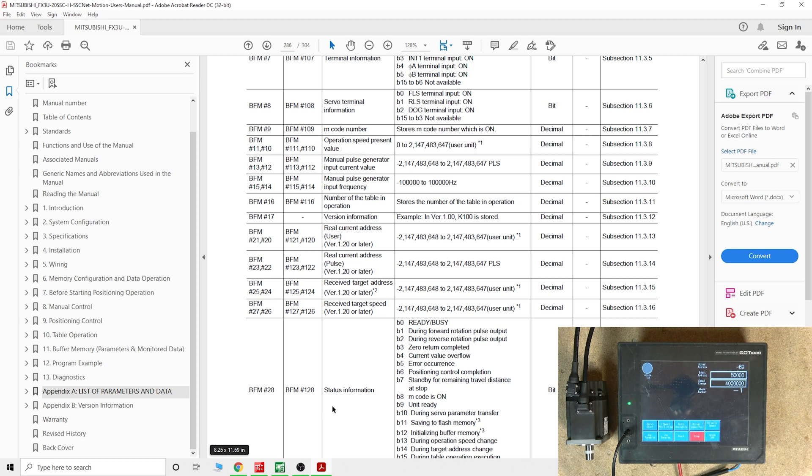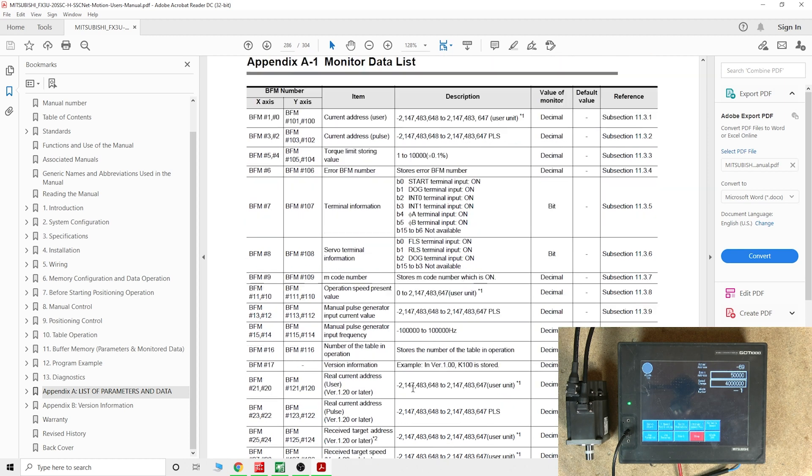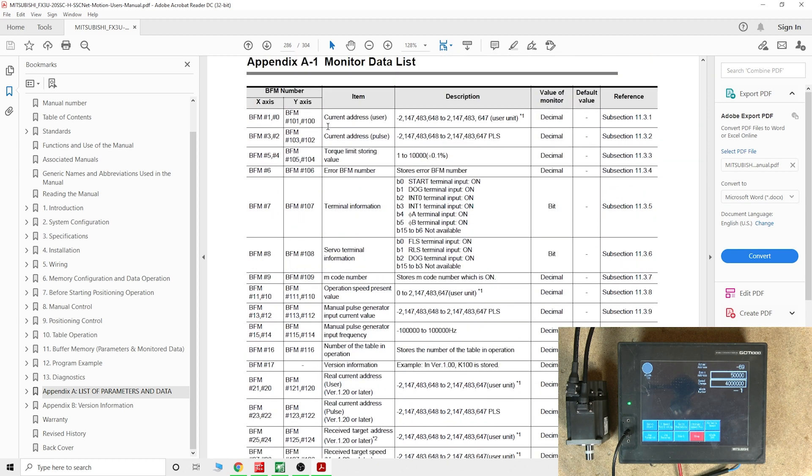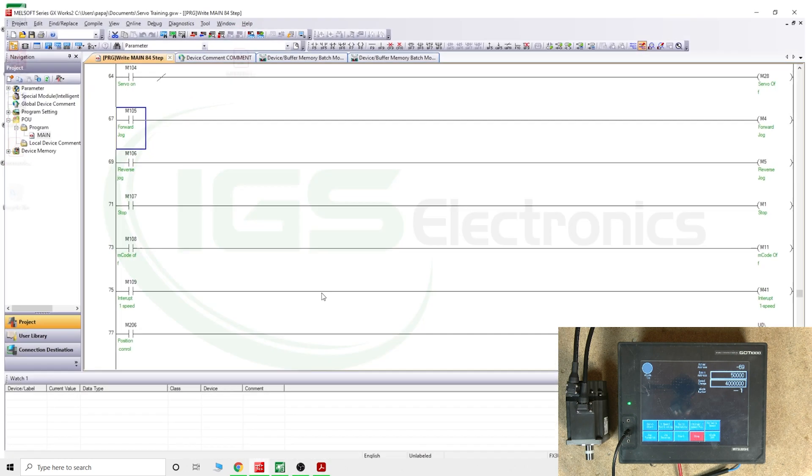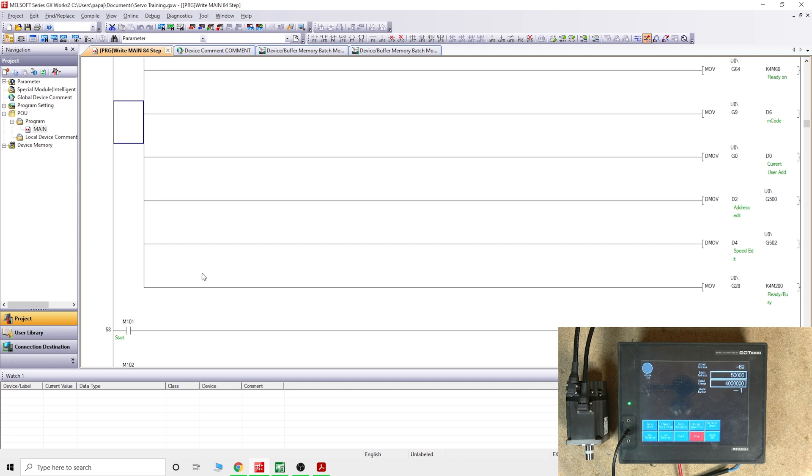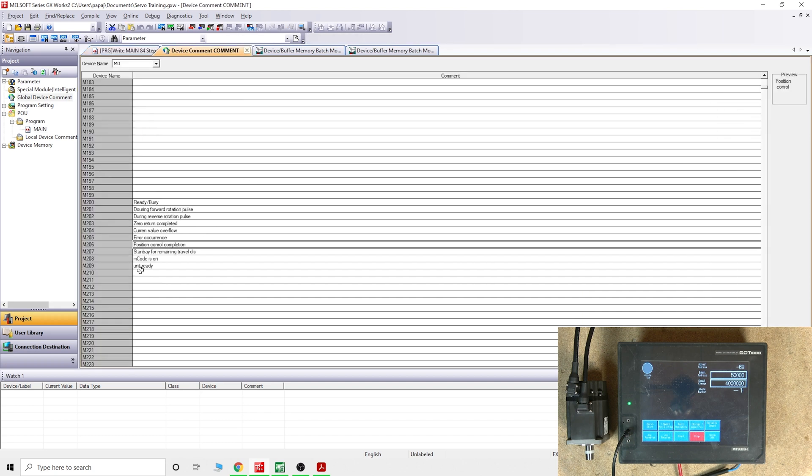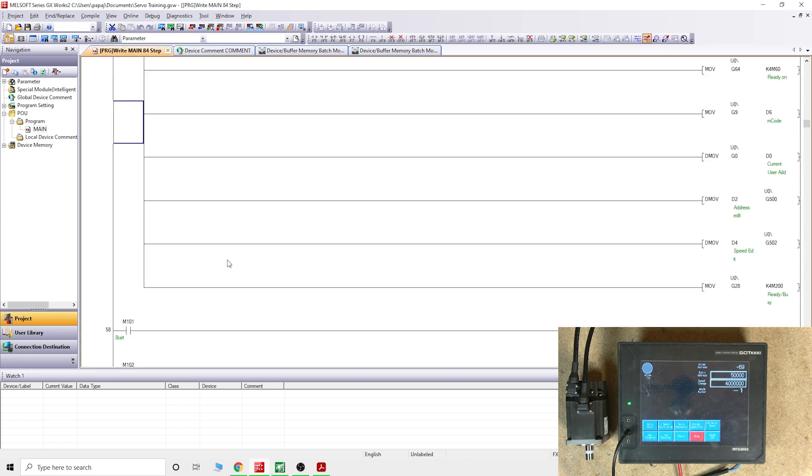We're going to use that to create some program for it. You remember from my last couple of videos we already have assigned and moved the buffer memory G2928 into K4 M200. If you look at my comments in here, that position control completion bit has been assigned to M206. So what we're going to do in here, we're taking this M206 and we're creating a MOVP, which is basically only once. Once you receive the signal, it pulses, and that is it. It's going to move K0 into G0.